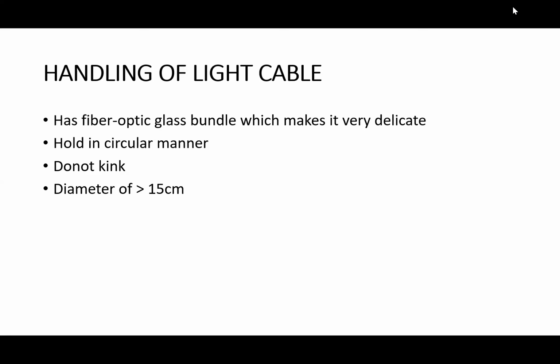Now, the light cable, of course, is a fiber optic glass bundle. This makes it very delicate. You know, the fiber optics, if you mishandle them, you damage the fibers inside the cable. So it is held in a circular manner. Don't kink it to form an acute angle.